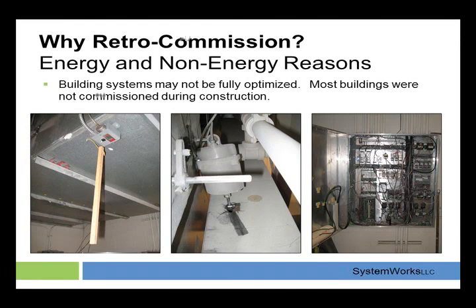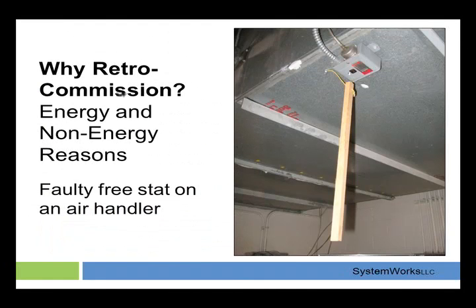So what we did is we just picked a few things, and we'll talk about them here, but these are some pictures that we found from an actual school in our area. The first picture is a low limit or a Freestat on an air handler. The Freestat's meant to stop the unit before it causes damage, before a coil freezes and you have water damage in the building. Well, what happened here is this Freestat tripped on a daily or more frequent basis, so instead of fixing the problem, they just put a stick on it so they could walk in every morning and start the unit back up. These are things we found in actual schools, and we find this kind of stuff every day.